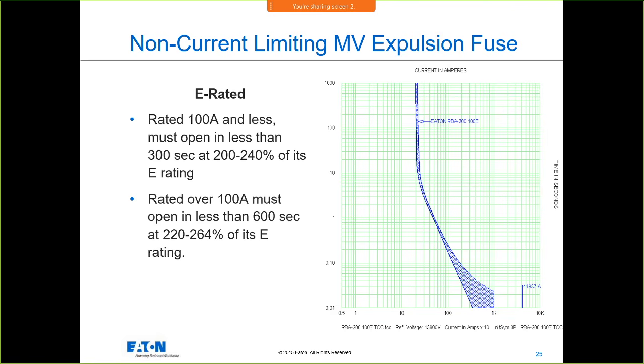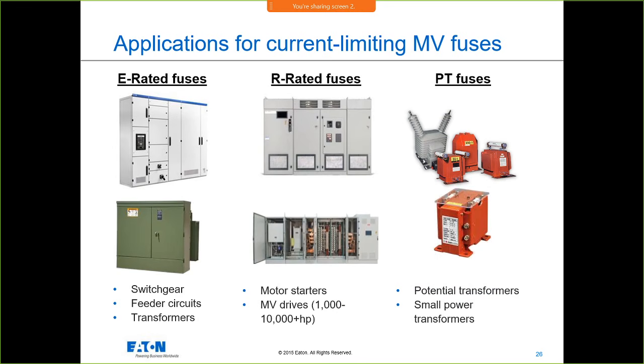Those let a lot through. This is your medium voltage. You can have these on the primary of a transformer, and they'll let through a lot of energy on the secondary of that transformer. This is where you'll see your E-rated and R-rated fuses, and your PT fuses.